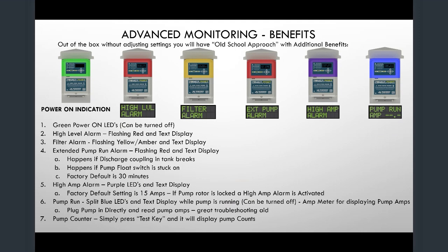There's a high amp setting you can go in and change. So all of our power posts are rated up to 15 amps, but if you're running a 7.8 amp pump, you can establish maybe half an amp higher than that. So if it ever starts drawing 8.3 amps or whatever you want to put in there, you would get a high amp alarm, and that would be good. Maybe the impeller's clogged or something like that. Or at the end of a pump cycle, as pumps age, their windings start to break down and they start to draw higher amps. So you could get an early pump failure warning, basically.